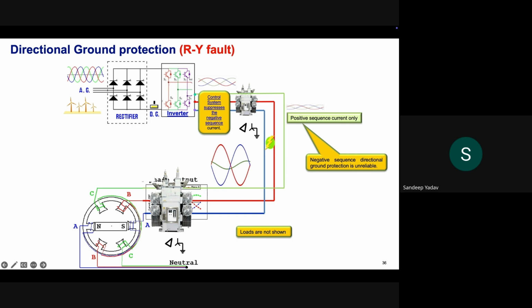And the vector group of the step-up transformers of these wind farms or solar power plants also has a role to play, as we'll see in the case of a single phase to ground fault. So we see that the response from the wind farm is only positive sequence, and there is no negative sequence current, or very little, and that is why the conventional relays will find it difficult to determine the directionality of this fault. So there are chances of maloperation of distance protection or the conventional line impedance protection.